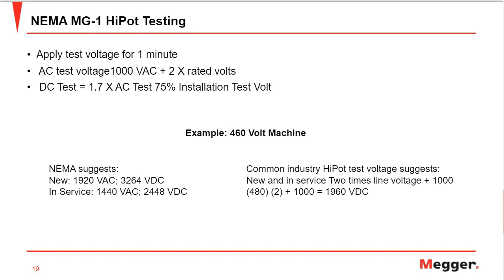Here we have an example of a 460 volt motor. For a new 460 volt motor, we'll use 3264 volt DC, while in service we'll use 2448 volt DC. And again, the same common industry high-pot test voltage, just multiplying the terminal voltage by a factor of 2 and adding 1000 to it.